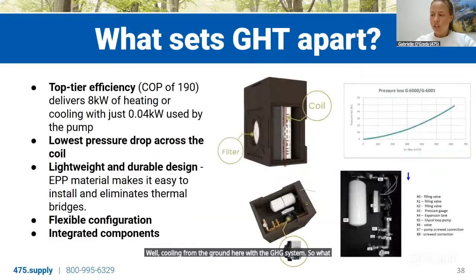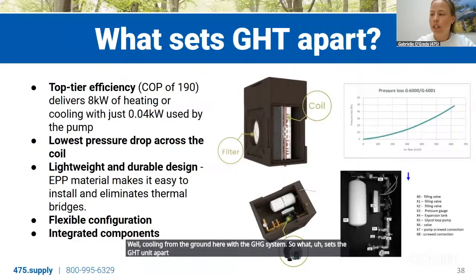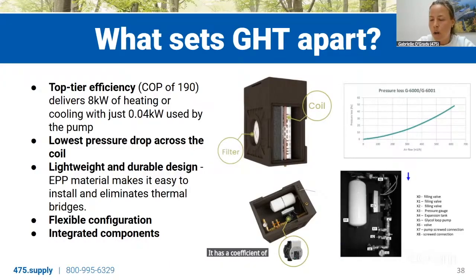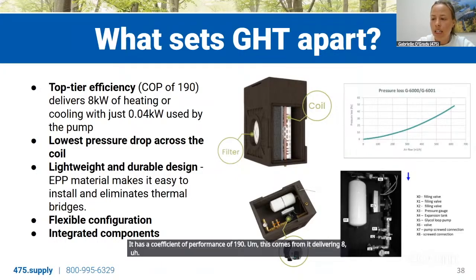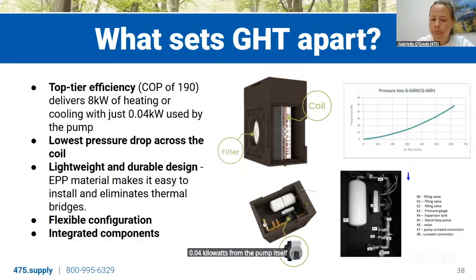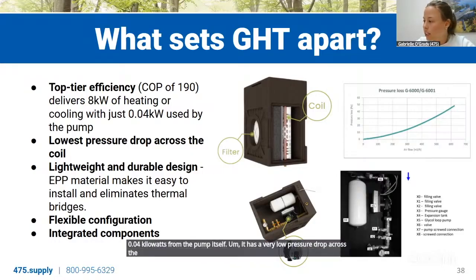So what sets the GHT unit apart from other geothermal preconditioning systems? It is, and why we selected it to carry with the FLAIR units, is because it has top tier efficiency. It has a coefficient of performance of 190. This comes from it delivering 8 kilowatts of heating or cooling with just 0.04 kilowatts from the pump itself. It has a very low pressure drop across the coil. You can see the curve to the right.